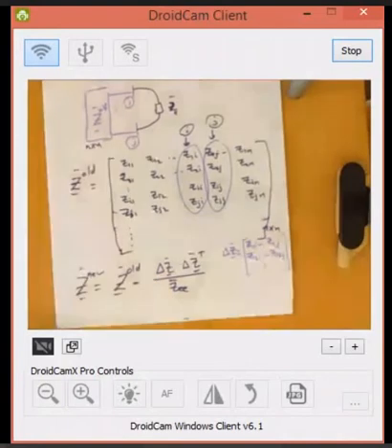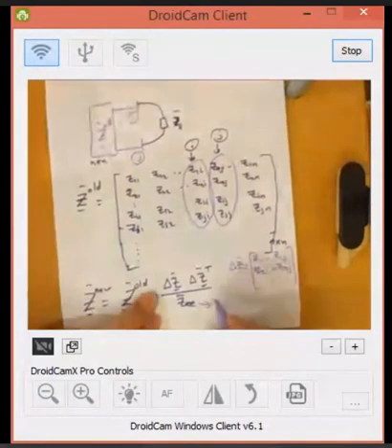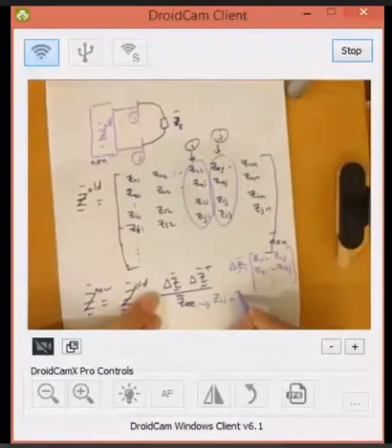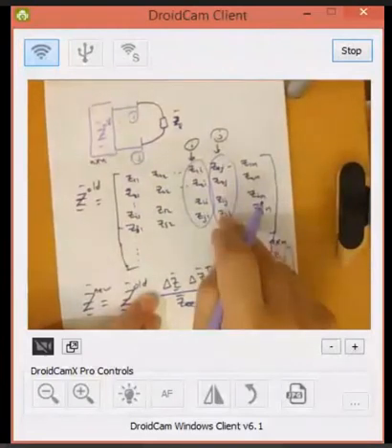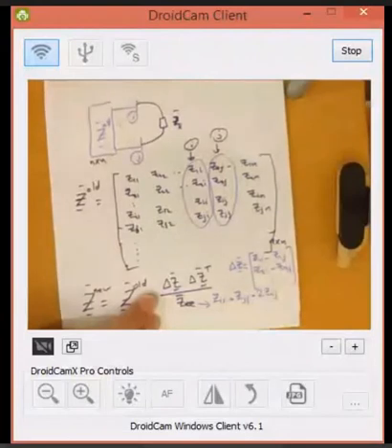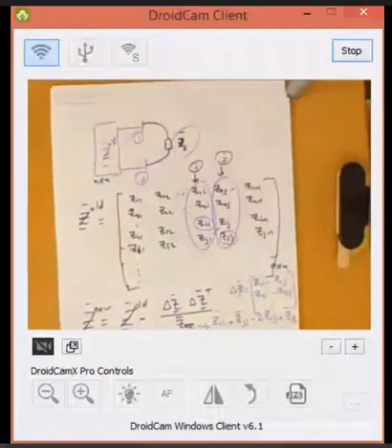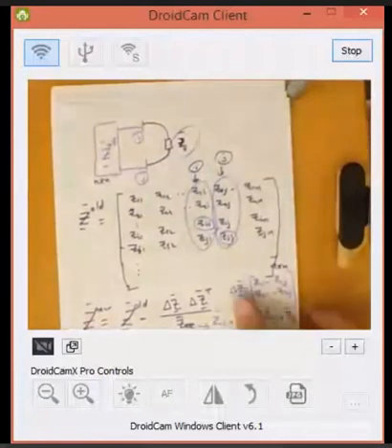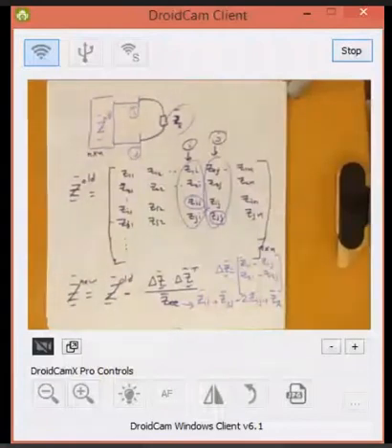And what is ZEE? It is connected between I and J, so it equals ZII plus ZJJ minus 2 ZIJ plus the value that I added, which is ZL. Any question here before we take an example?